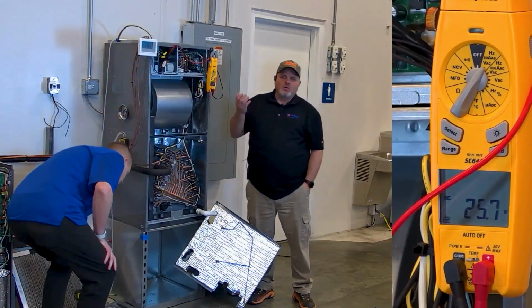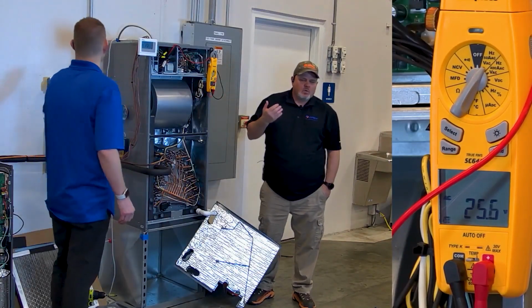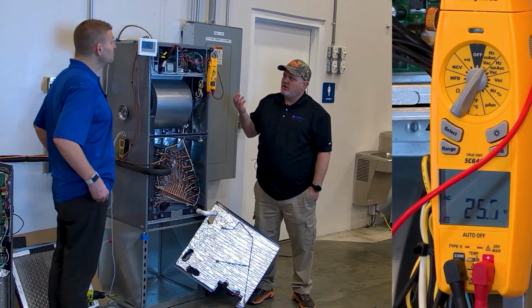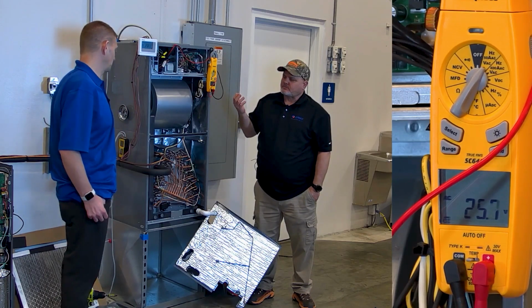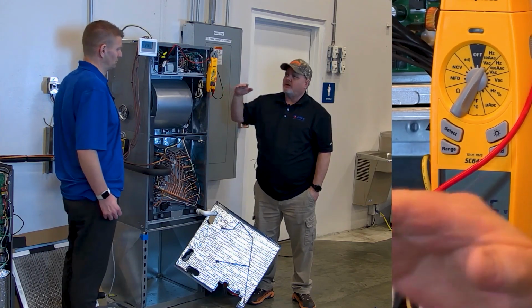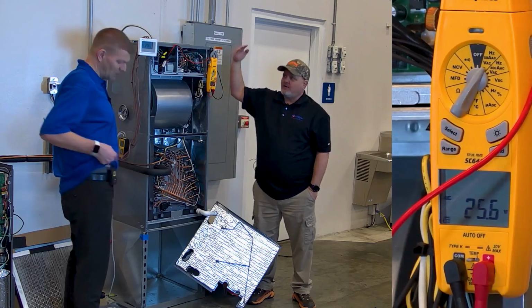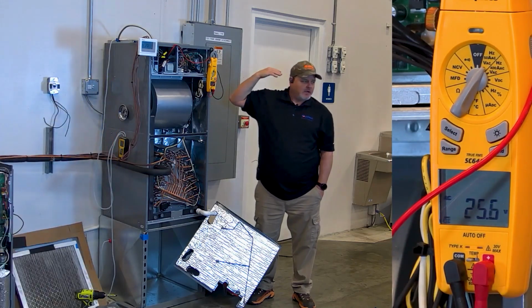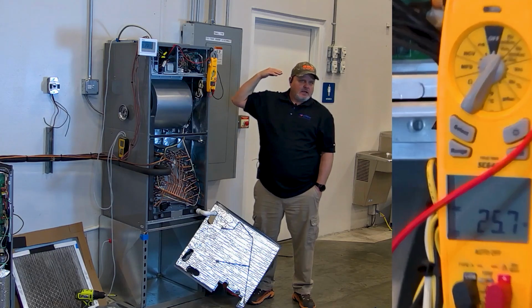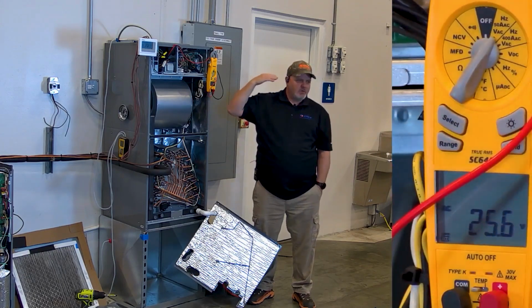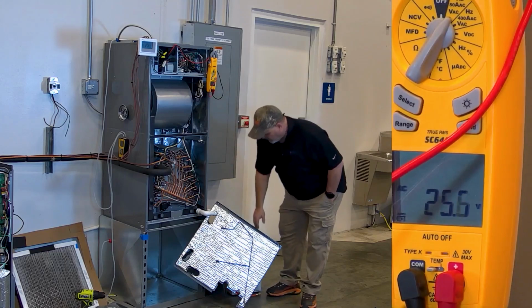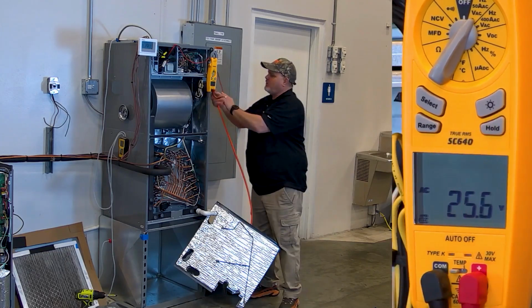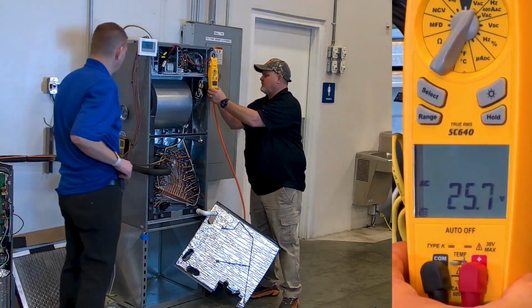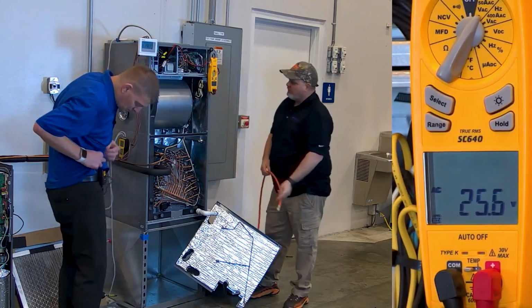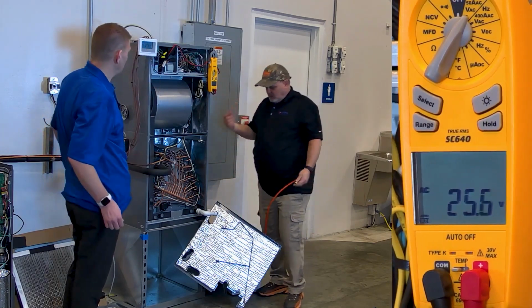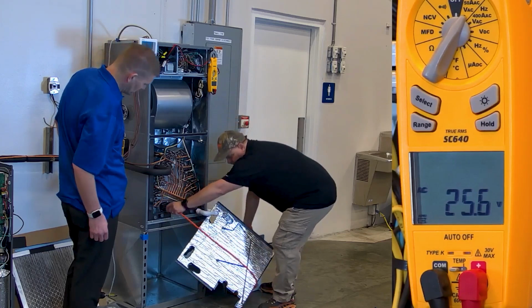I do know it works when you go into auxiliary heating, you know, heat pump running. If we elapse that 35-minute delay, and then we have it at 2-degree differential, it will bring on aux heat. So we've proven that. You kind of focus in on this meter here. It's showing the 25 volts. Let's see if it does it when it goes into alarm.